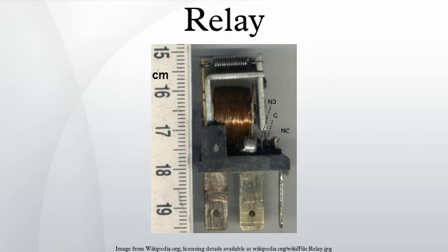Machine tool relay. A machine tool relay is a type standardized for industrial control of machine tools, transfer machines, and other sequential control. They are characterized by a large number of contacts which are easily converted from normally open to normally closed status, easily replaceable coils, and a form factor that allows compactly installing many relays in a control panel. Although such relays once were the backbone of automation in such industries as automobile assembly, the programmable logic controller mostly displaced the machine tool relay from sequential control applications.